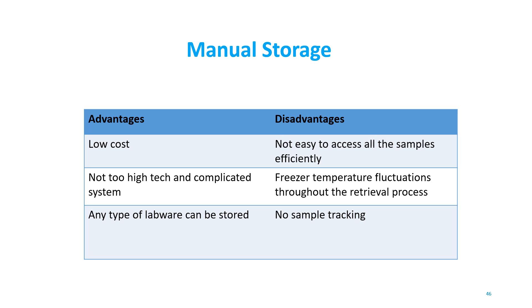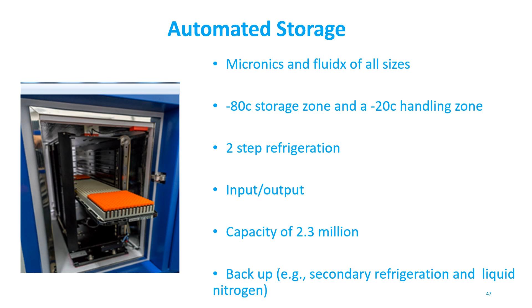About the automated storage. We implemented our automated storage in 2018. There are different types of microtubes and different sizes. We have a -80 storage zone and a -20 handling zone, with two steps of refrigerating, input and output. The capacity of the automated store is 2,300,000 samples. The backup will be secondary refrigeration and liquid nitrogen in this automated biostore in our laboratory.